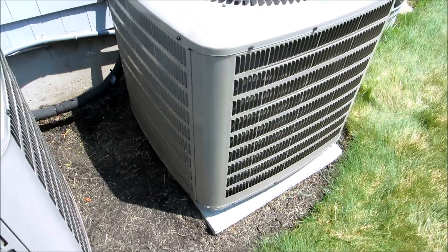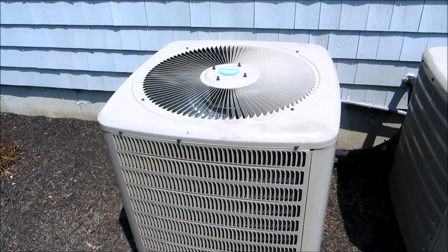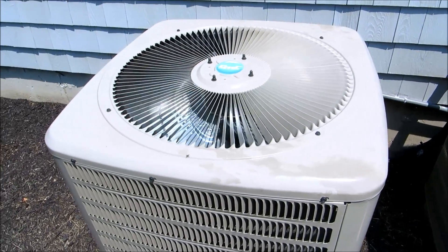I'm going to check for a P-trap on that second floor unit when I get access. This one in the basement is the one I fixed. When I get some time, I'll come back, reclaim all the refrigerant, and do a fresh charge.